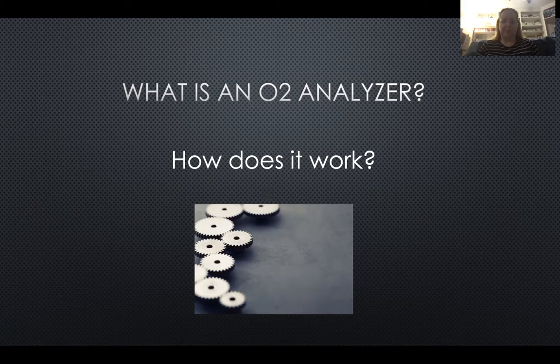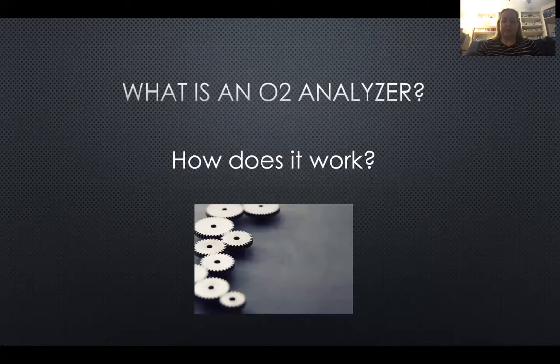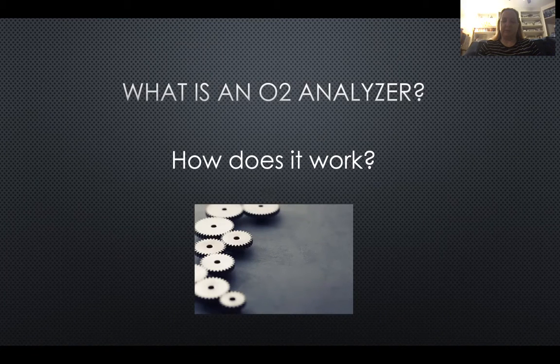How does it work? Basically, it works by a chemical reaction that occurs between chemicals like potassium hydroxide and oxygen. This reaction creates an electronic potential. The sensor contains a cell with electrodes. When O2 comes in contact with that cell, the potential developed will be proportionate to the O2 concentration. The cell is called an electrogalvanic fuel cell.